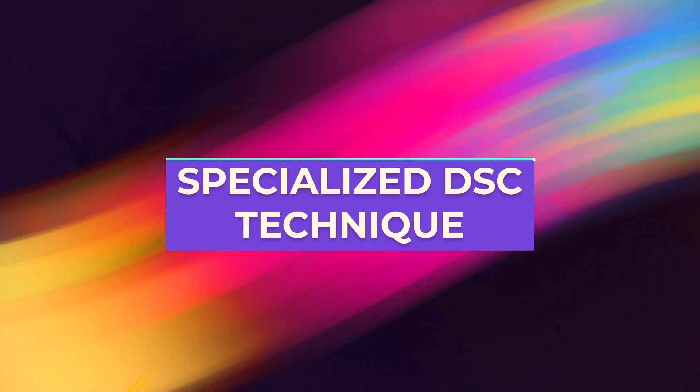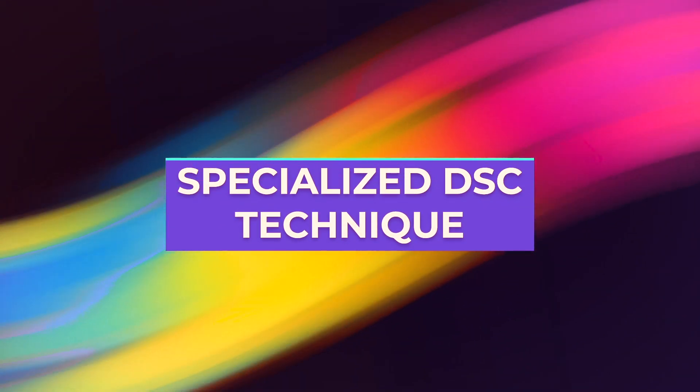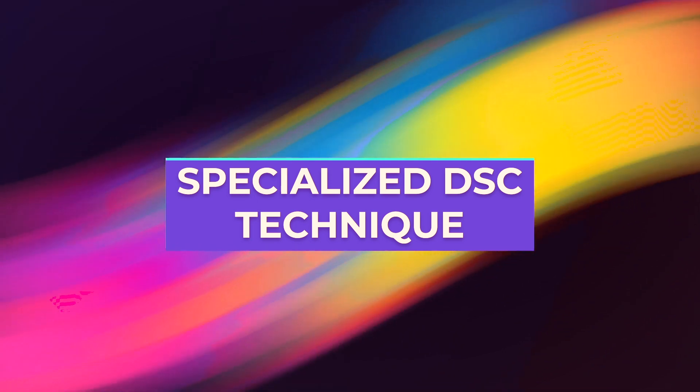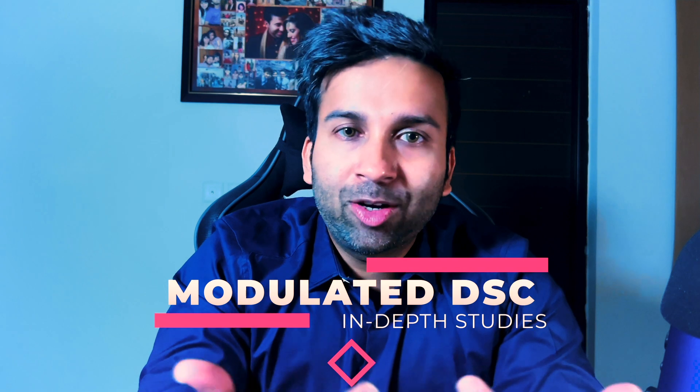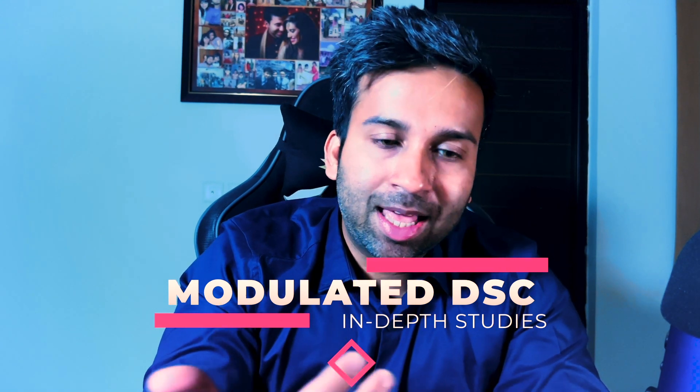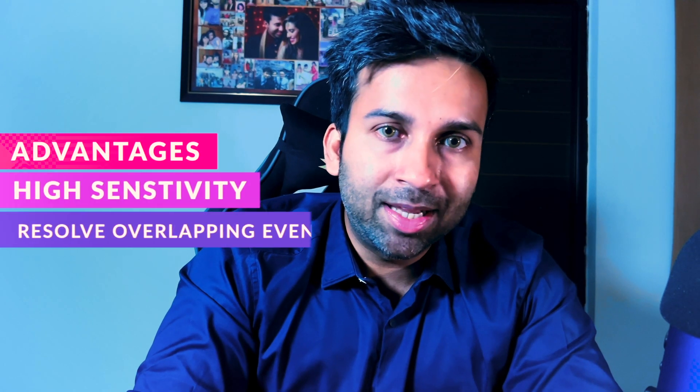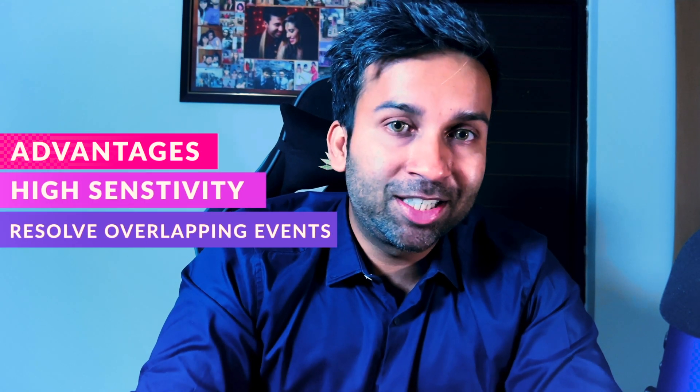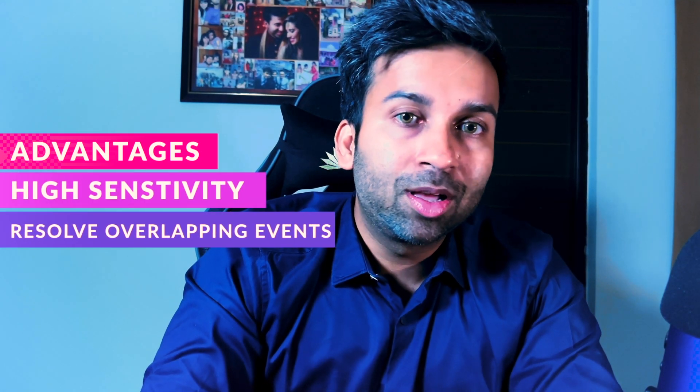Now let's jump to the most interesting section where a specialized DSC technique shall be discussed. This is called the modulated DSC technique. The main drawback of the conventional DSC is that it cannot resolve overlapping transitions, which is where modulated DSC comes into the picture, where it can clearly resolve what's called the reversing and the non-reversing processes, which we shall discuss shortly. Another advantage of MDSC is that it has increased sensitivity compared to conventional DSC.